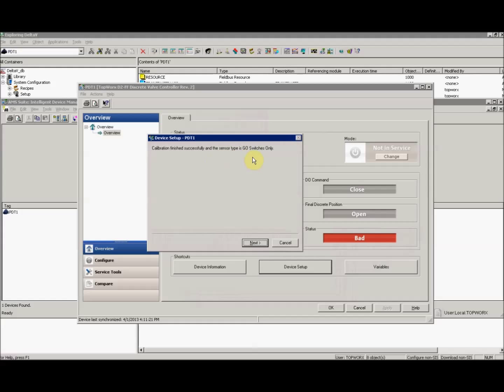It's telling me the calibration has finished successfully and the sensor type is switches only. The device can sense what sensors it has terminated on it, whether a potentiometer or switches. And it does this on the first calibration of the device and stores that data. If for whatever reason you hook up more sensors down the road, you'll need to perform a factory restore, terminate devices, and then recalibrate.